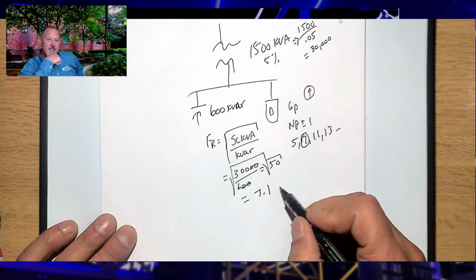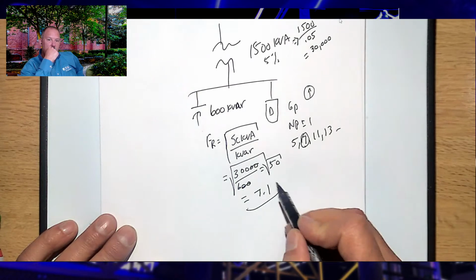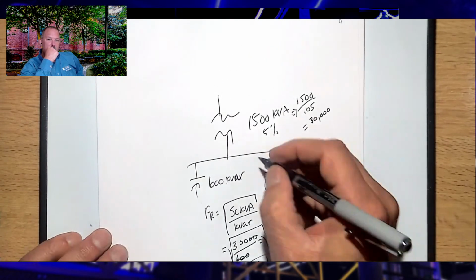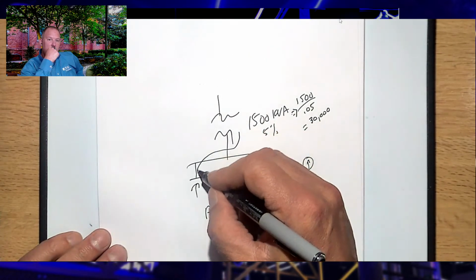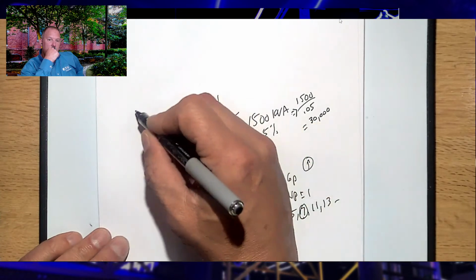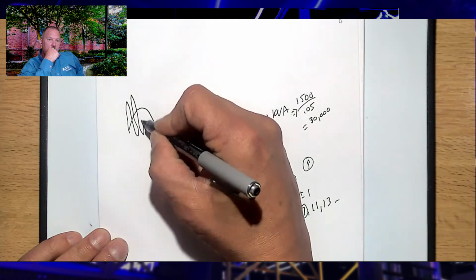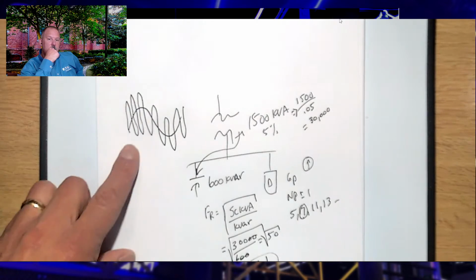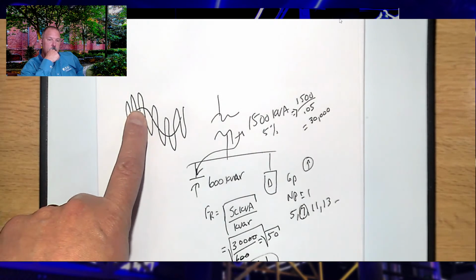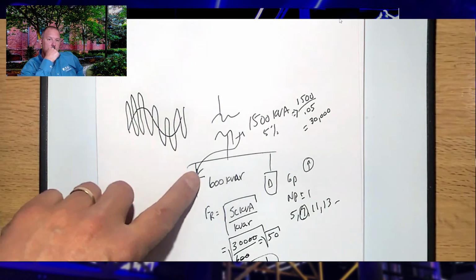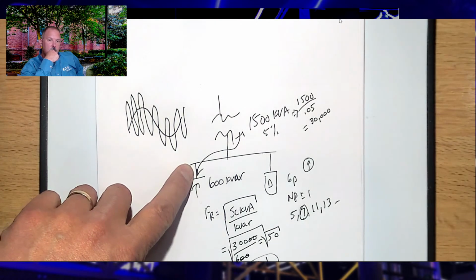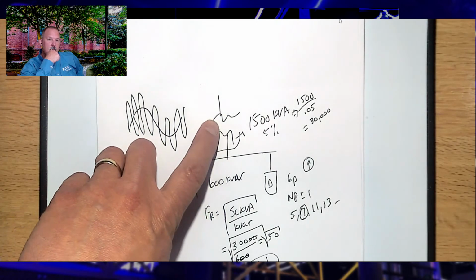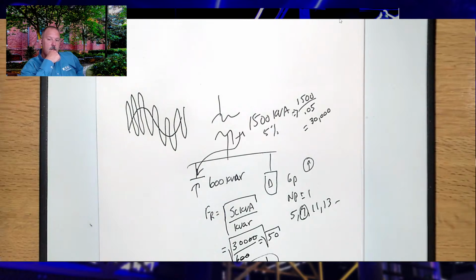I could tell. So this seventh harmonic that's produced by my drive is going to get amplified. And what you're going to see in this circuit between these two is your 60 hertz current, sort of, but then you're going to see this seventh harmonic current superimposed over top of it. This really big seventh harmonic current. And that's going to either blow up the capacitor, blow the fuses, or hopefully it doesn't, but it could also fail your transformer.